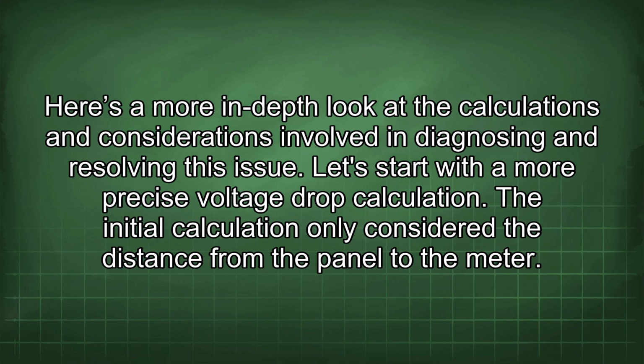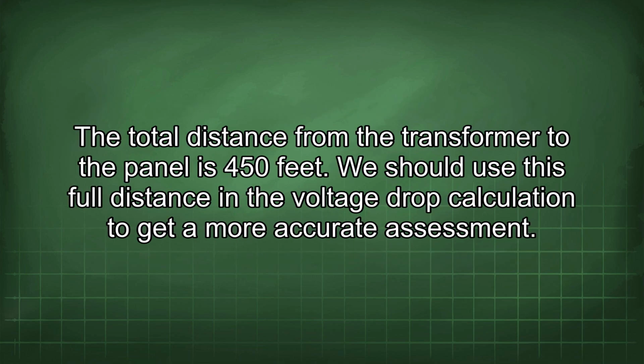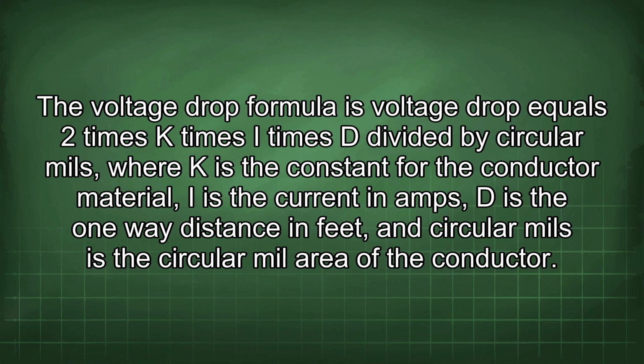Let's start with a more precise voltage drop calculation. The initial calculation only considered the distance from the panel to the meter. The total distance from the transformer to the panel is 450 feet. We should use this full distance in the voltage drop calculation to get a more accurate assessment. The voltage drop formula is voltage drop equals 2 times K times I times D divided by circular mils, where K is the constant for the conductor material, I is the current in amps, D is the one-way distance in feet, and circular mils is the circular mil area of the conductor.